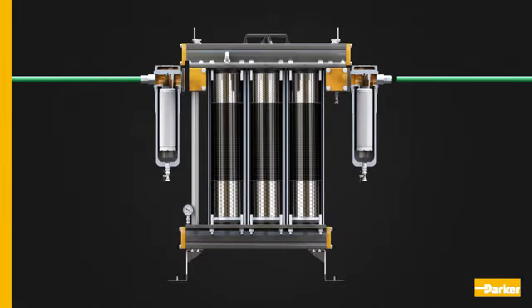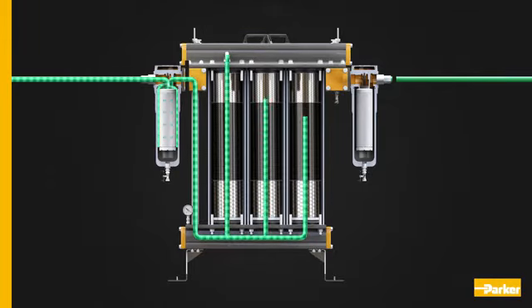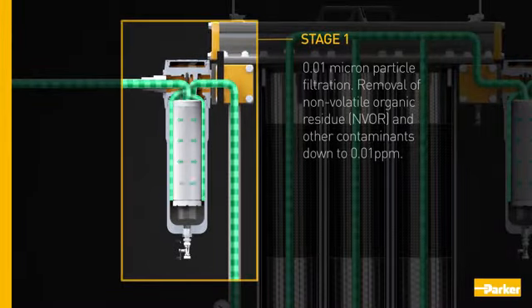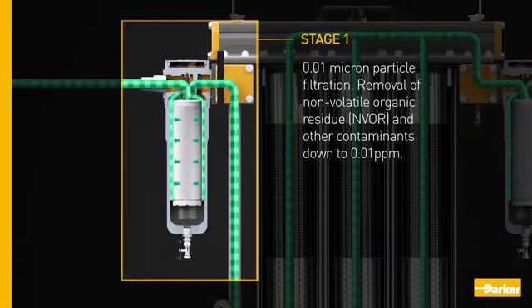pCO2 offers five stages of carbon dioxide purification in a compact modular system to offer the highest level of production plant and point-of-use protection. Stage 1: 0.01 micron particle filtration — removal of non-volatile organic residue and other contaminants down to 0.01 ppm.